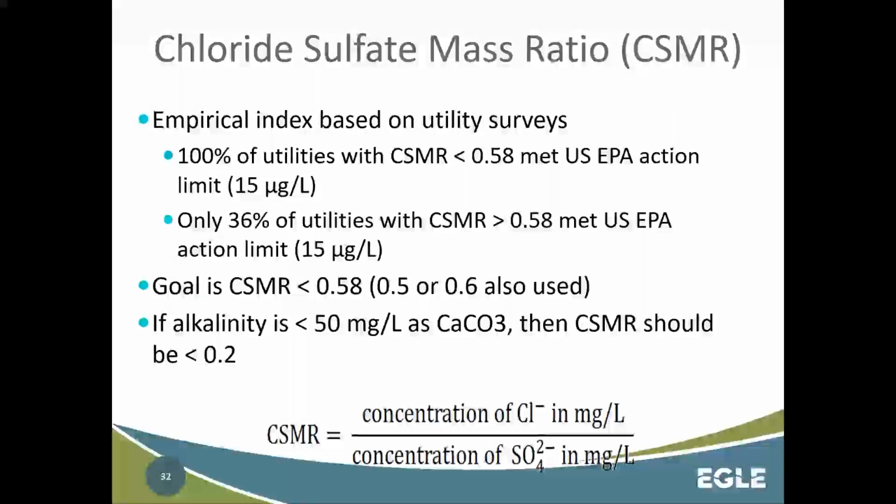Another one, we briefly touched on it, is the chloride sulfate mass ratio. Essentially, you're taking the concentration of chloride over the concentration of sulfate to get your CSMR value. And CSMR is built on empirical knowledge rather than actual fundamental proof, something we don't fully understand yet.